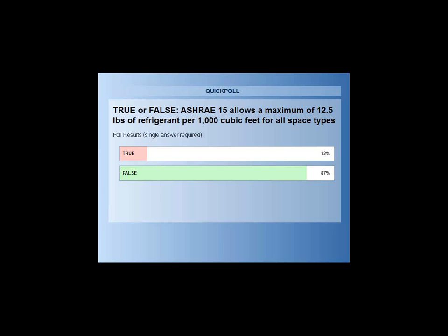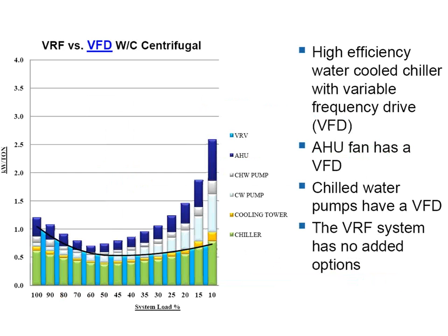Jonathan has a good question that I forgot to mention. So Jonathan asks if that chart I had showed, I'll put it back up for you guys. Well, let me get rid of the other thing. If this particular chart I got up on the screen accounted for the ventilation costs associated with the VRF, and no, it does not account for that. That is a good point, and that, in terms of this chart, is in favor of the VRF system. In many cases, as you might expect, a VRF system is coupled with a dedicated outside air unit, so those green or baby blue bars for VRF would go up somewhat for the ventilation equipment, if you will.